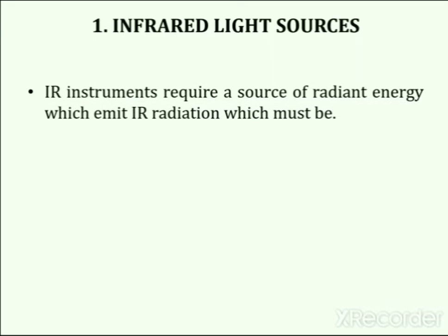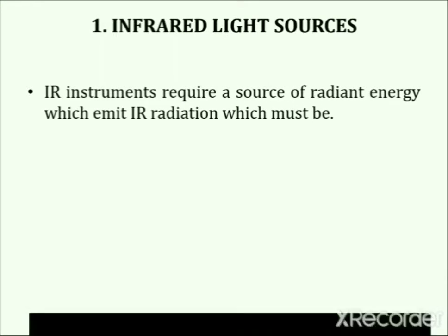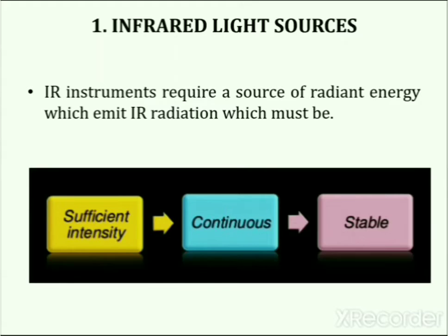An infrared instrument requires a source of radiant energy that emits IR radiation. A good light source must have the following characteristics: it should produce the desired radiation with sufficient intensity, the radiation should be continuous, and the light source should be stable over a long period of time.